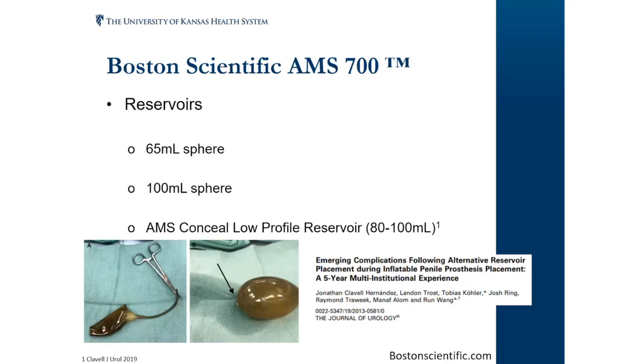Now, this is a study from Dr. Clavel looking at failure rates of over 500 AMS devices, and they found a disproportionate number of failures in Conceal reservoirs that were filled to less than 80 milliliters. What you can see in figure A is almost a dimpling effect when they pulled this reservoir out of the patient because it was completely empty. And what they noticed when they filled the reservoir is this pinhole defect at the top.